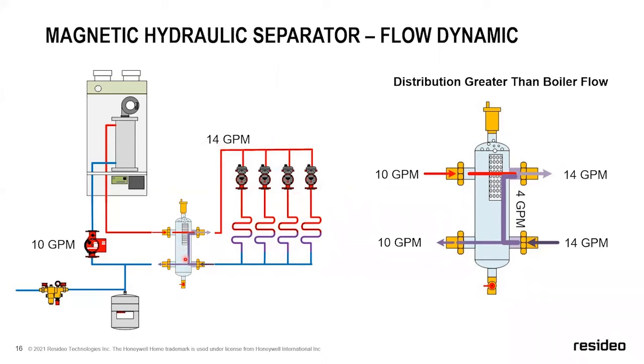And I kind of lost my train of thought on the previous slide, but what's taking place is, since there is no pressure difference here, my first manager used to tell me that, you know, water's lazy. It's going to take the path of least resistance. So since there's no pressure loss in here, and the pumps are creating more of a pressure differential, there's no reason for that water to push any extra flow out here. It's just going to take the easiest path, which is right back to the suction of the circulators. And that's where you get this flow dynamic taking place.